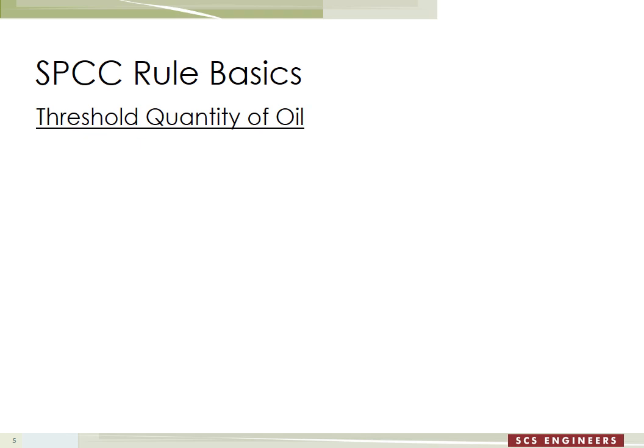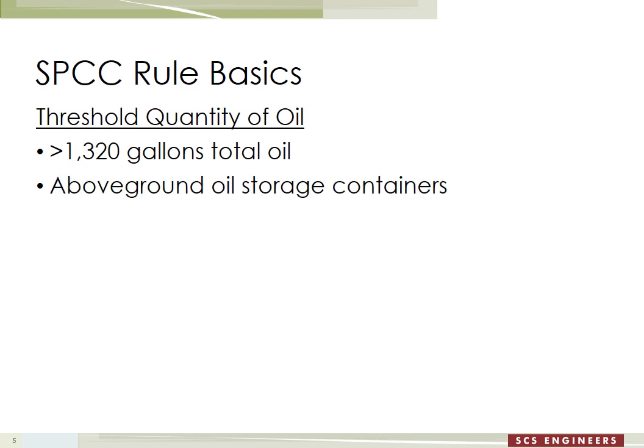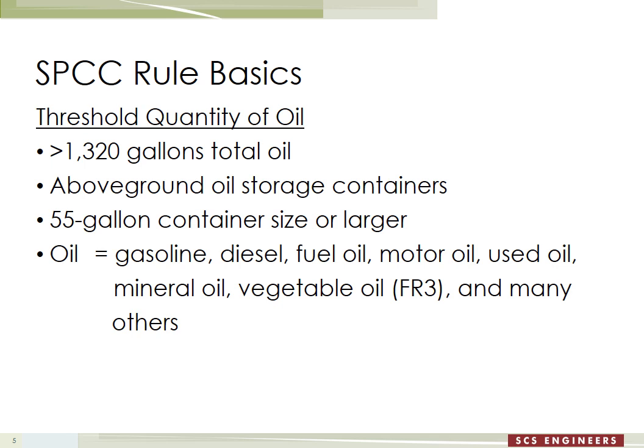The SPCC rule applies to facilities that store more than 1,320 gallons of oil in above-ground oil storage containers, with a few exceptions for underground storage. We're talking about containers that are 55 gallons in size or larger — the rule does not apply to anything smaller than 55 gallons. Oil is a broad definition; the most common types at your facilities include gasoline, diesel, fuel oil, motor oil, used oil, mineral oil, vegetable oil — including FR3, which is marketed as environmentally friendly but still falls under the SPCC rule.